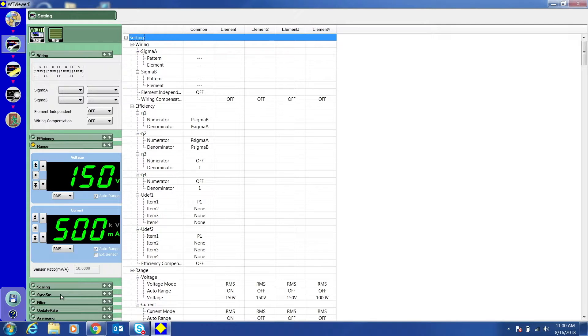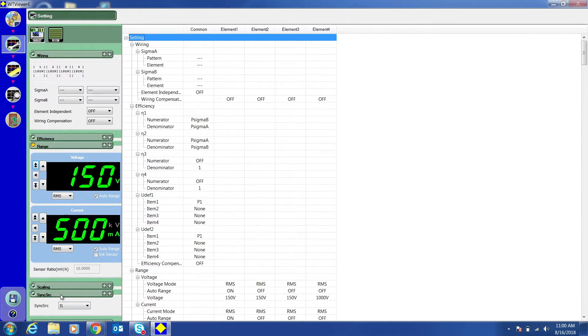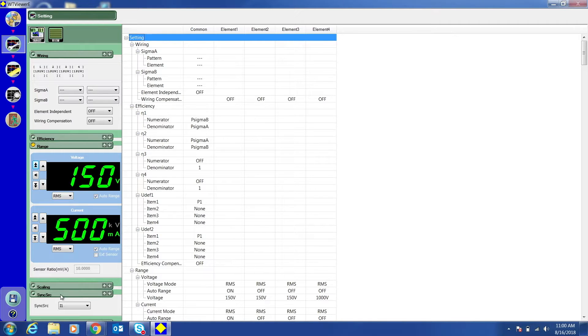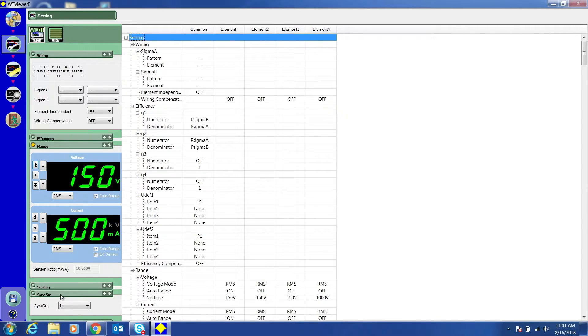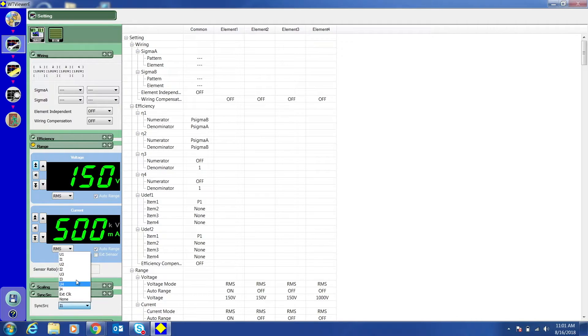Click Sync Source. The synchronization source defines the period over which the sample data is acquired for determining the numeric data. Select an input signal with a stable input level and frequency for the sync source.